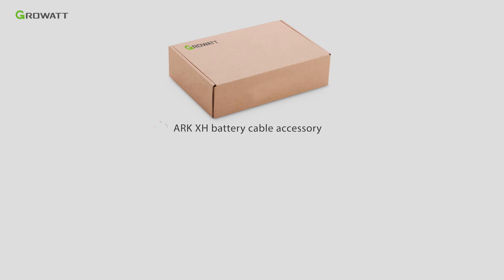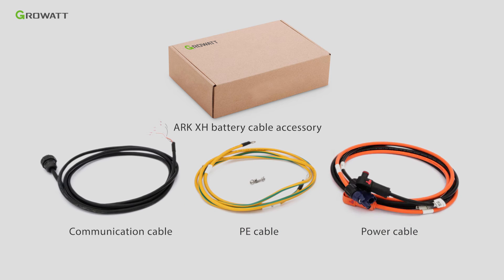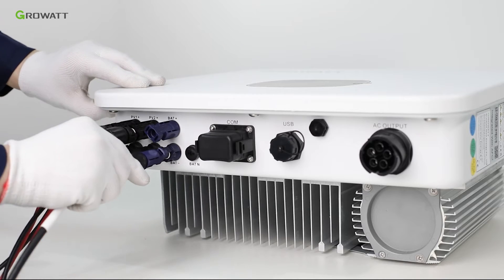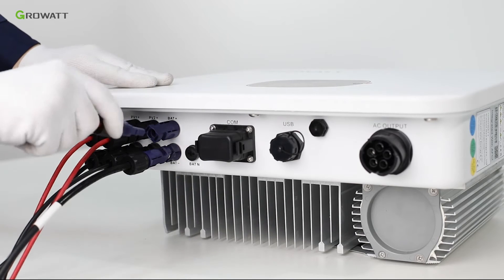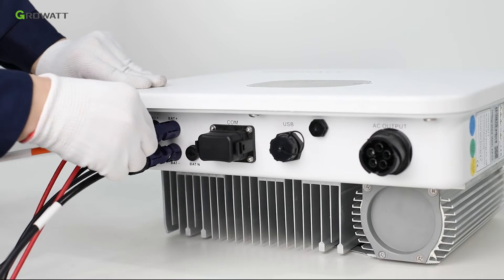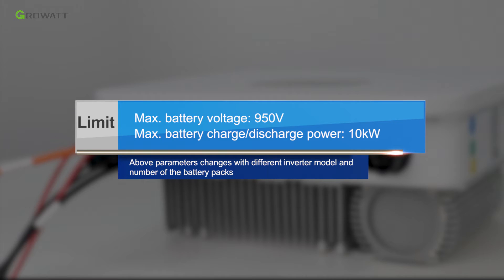The battery power cable is inside the package for the ARK XH battery cable accessory, which is purchased from GROWATT. Insert the battery positive and negative cable into the relative battery terminal of the MODXH inverter. Limits: maximum battery voltage 950V; maximum battery charge and discharge power 10 kW.